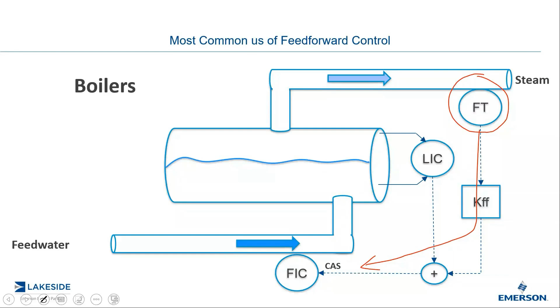Because that load disturbance is coming, and in an ideal world a pound of steam equals a pound of water. So if steam goes up by 1,000 pounds, I should add 1,000 pounds of water right away. If I do it the right way, the right time, and the right amount, the level controller should not see any changes. Obviously, this is an ideal situation.